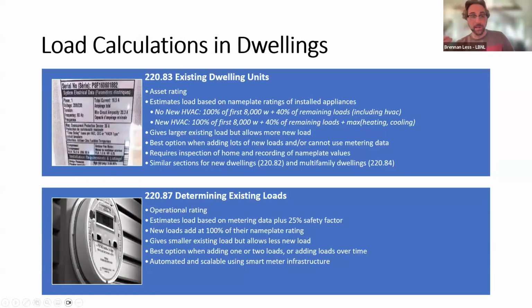Load calculations in dwellings, again focused on existing dwellings. There's two main ways, both optional paths within the code. The first is 220.83. It's basically going around, doing an inventory of the loads in the house, adding them up, and then applying an adjustment factor for the fact that they're not all operating at the same time.